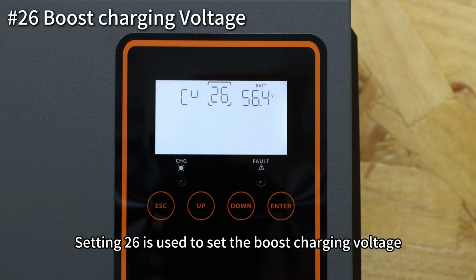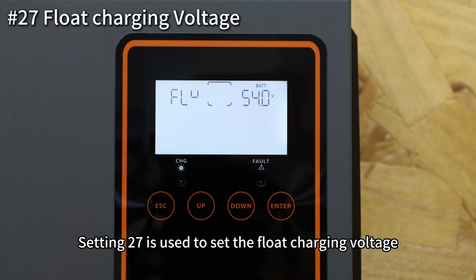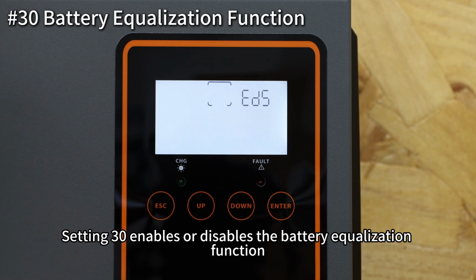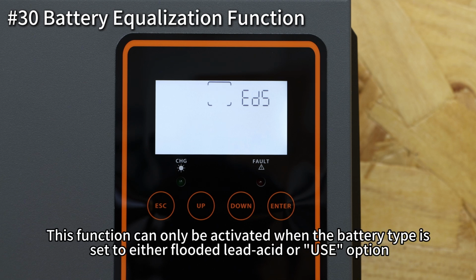Setting 26 is used to set the boost charging voltage. Setting 27 is used to set the float charging voltage. Setting 30 enables or disables the battery equalization function. This function can only be activated when the battery type is set to either flooded lead-acid battery or the "USE" option.